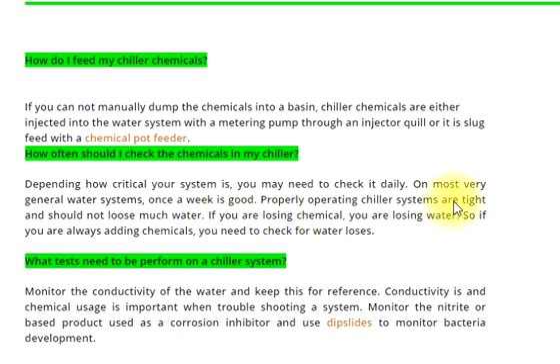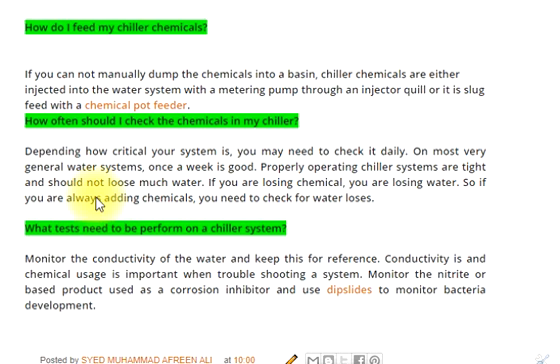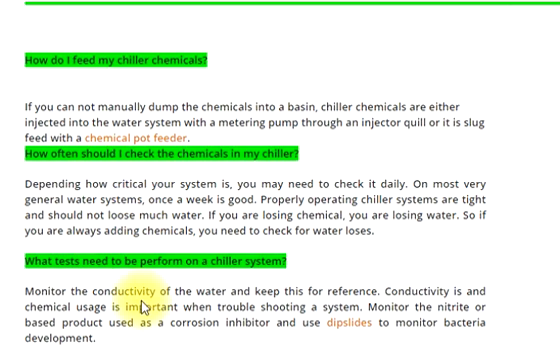Properly operating chiller systems are tight and should not lose much water. If you are losing chemical, you are losing water. So if you are always adding chemicals, you need to check for water losses.